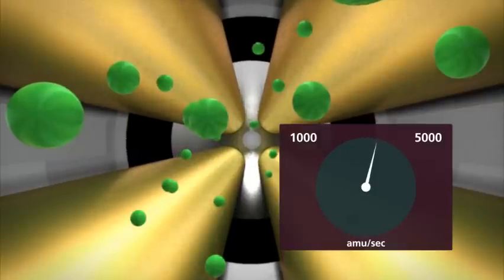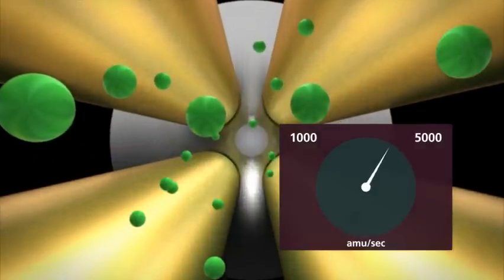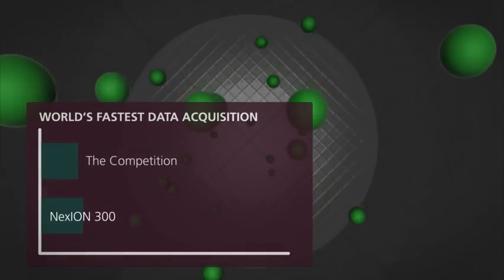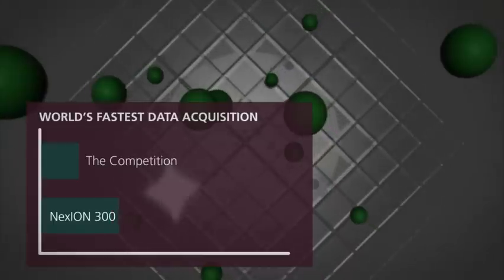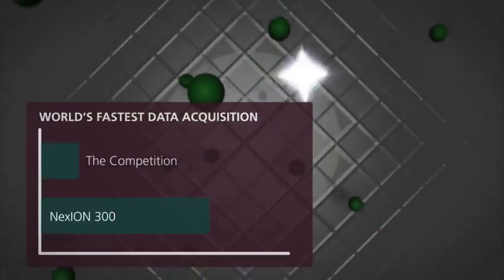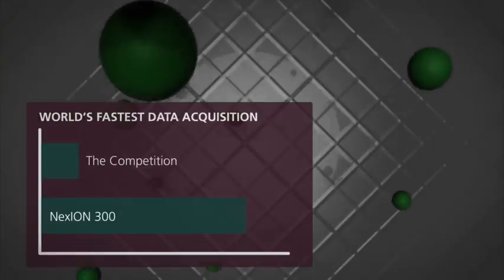Capable of the highest mass range attainable in an ICP-MS, Nexion's analyzing quadrupole refines the analyte beam with a final mass-to-charge filtration and focuses it on the fastest, state-of-the-art dual-mode detector that provides over nine orders of dynamic range.